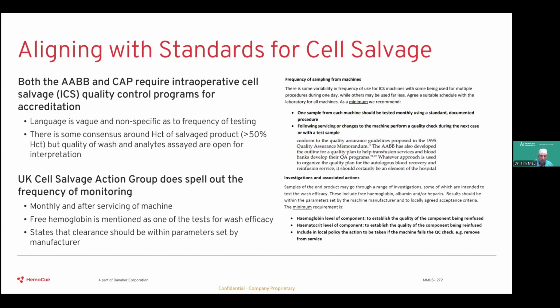And there is some consensus around stating that the hematocrit of a salvaged blood product is greater than 50%. But quality of wash or the analytes that you assay in your returned product are open for interpretation. So neither the AABB nor CAP tell you what exactly you should be assaying for within your cell salvaged return product. The UK Cell Salvage Action Group does spell out frequency of monitoring. The UK group does recommend monthly or after servicing of a machine within a hospital setting. The UK system does mention free hemoglobin as one of the tests for wash efficiency, and it states that the clearance of anything that you're analyzing should be within the parameters set by the manufacturer.